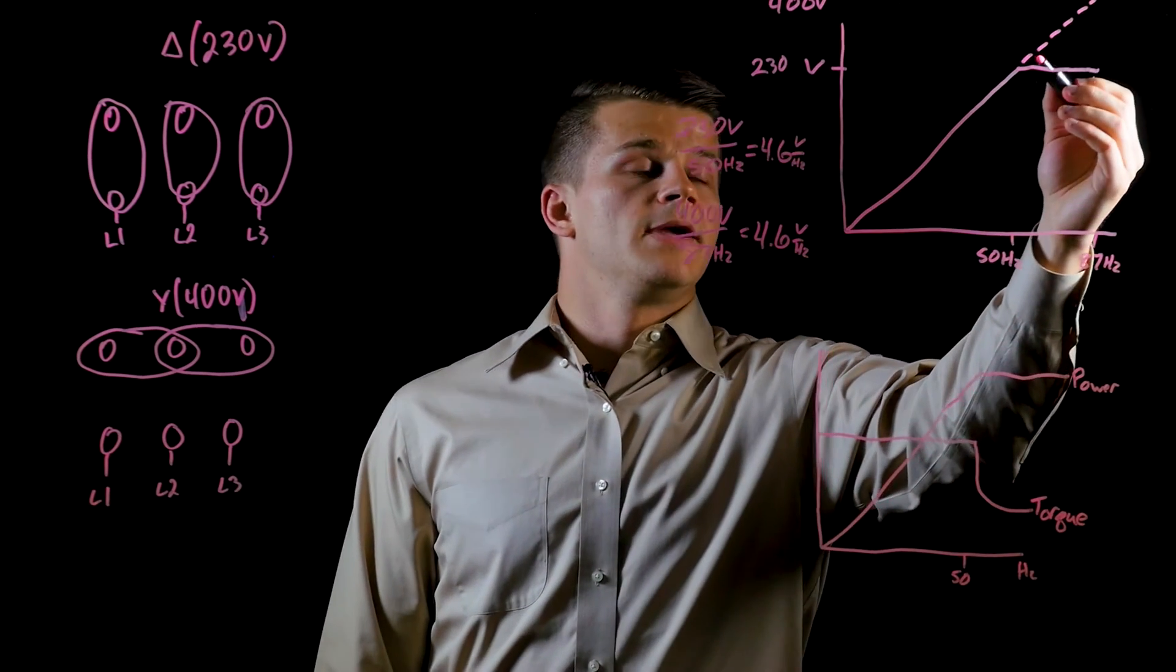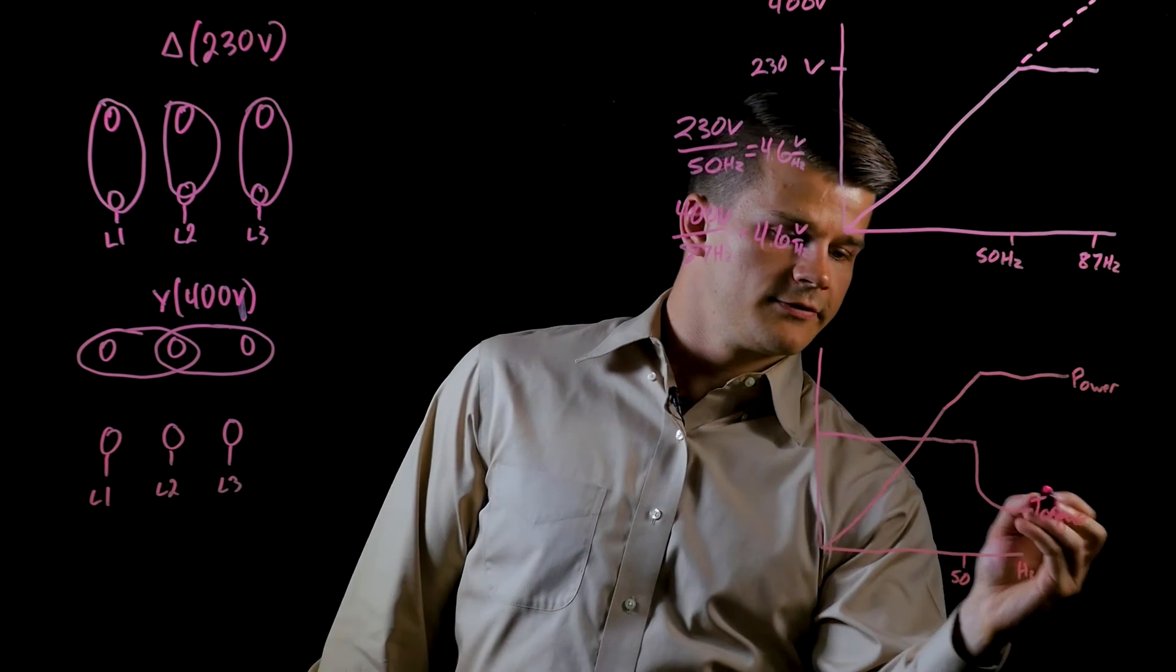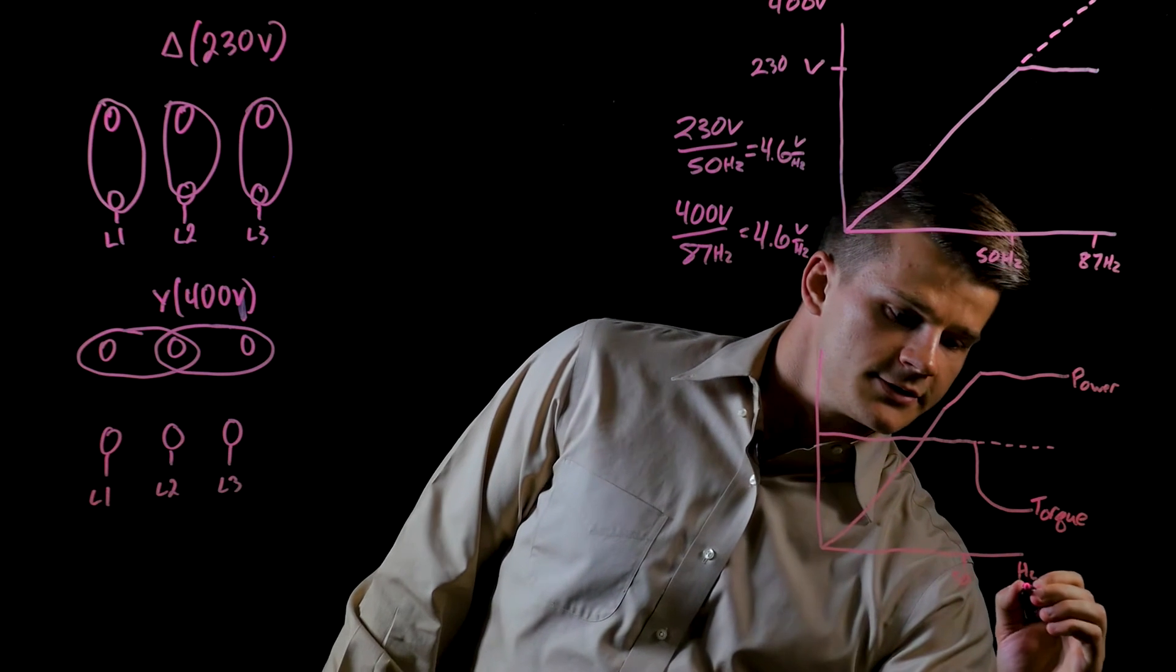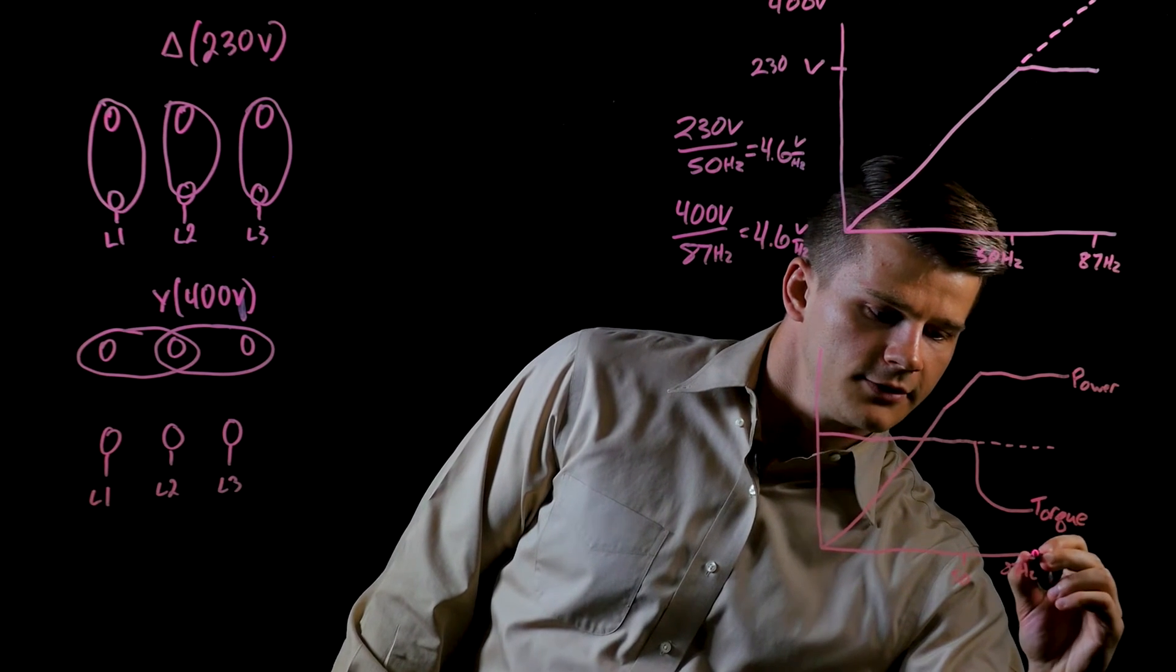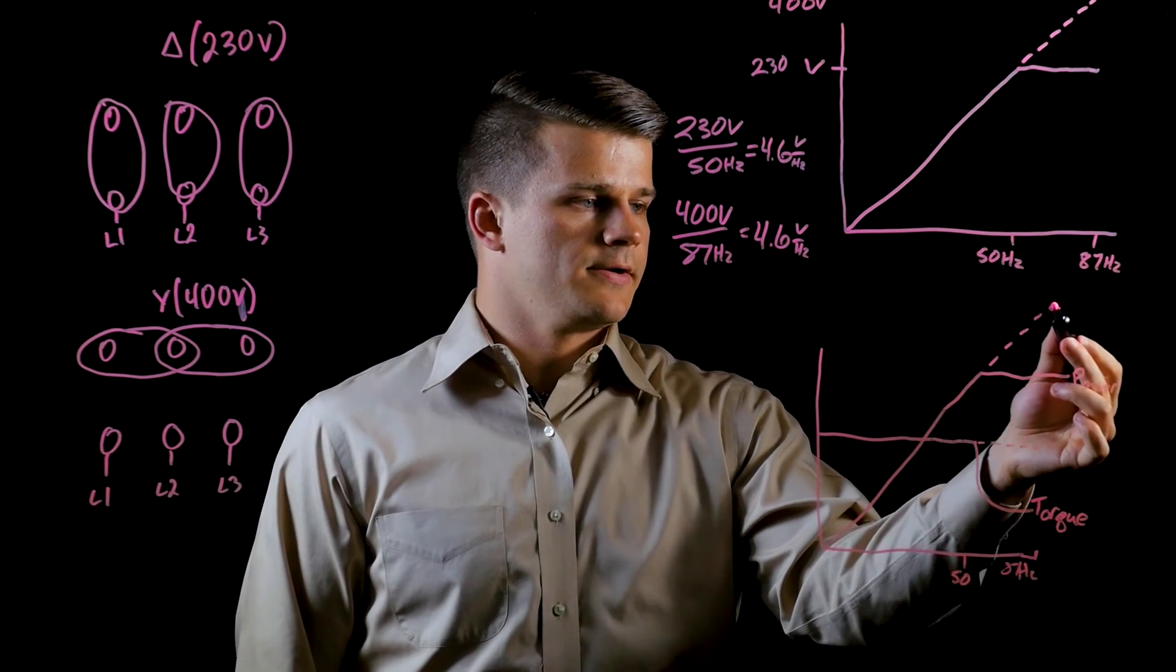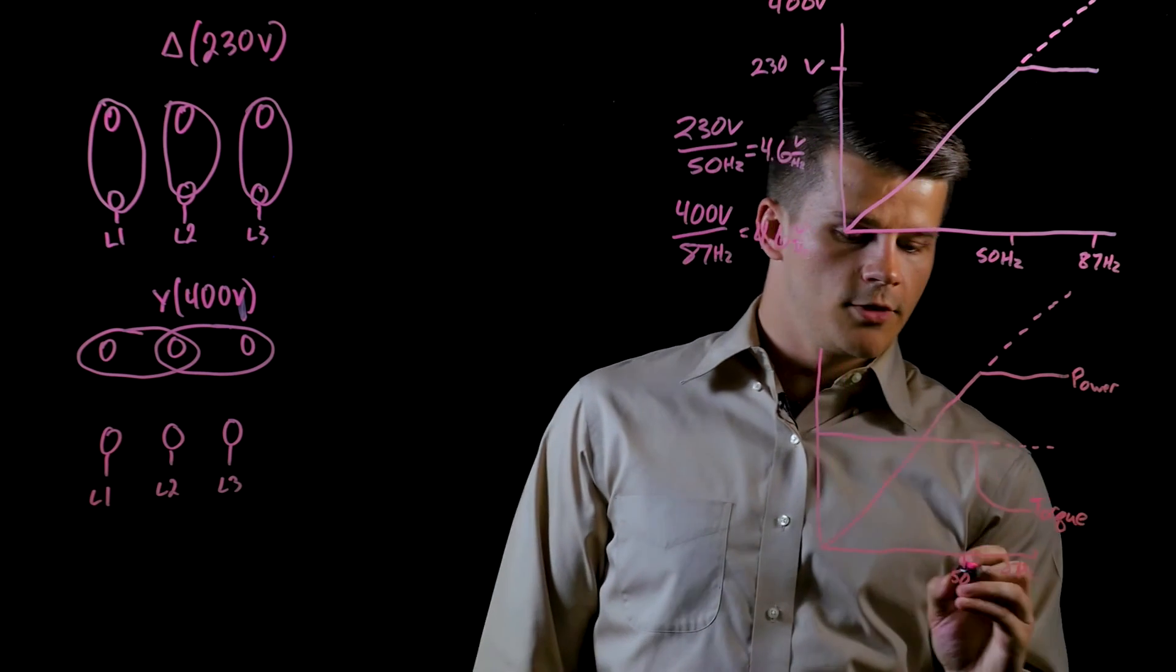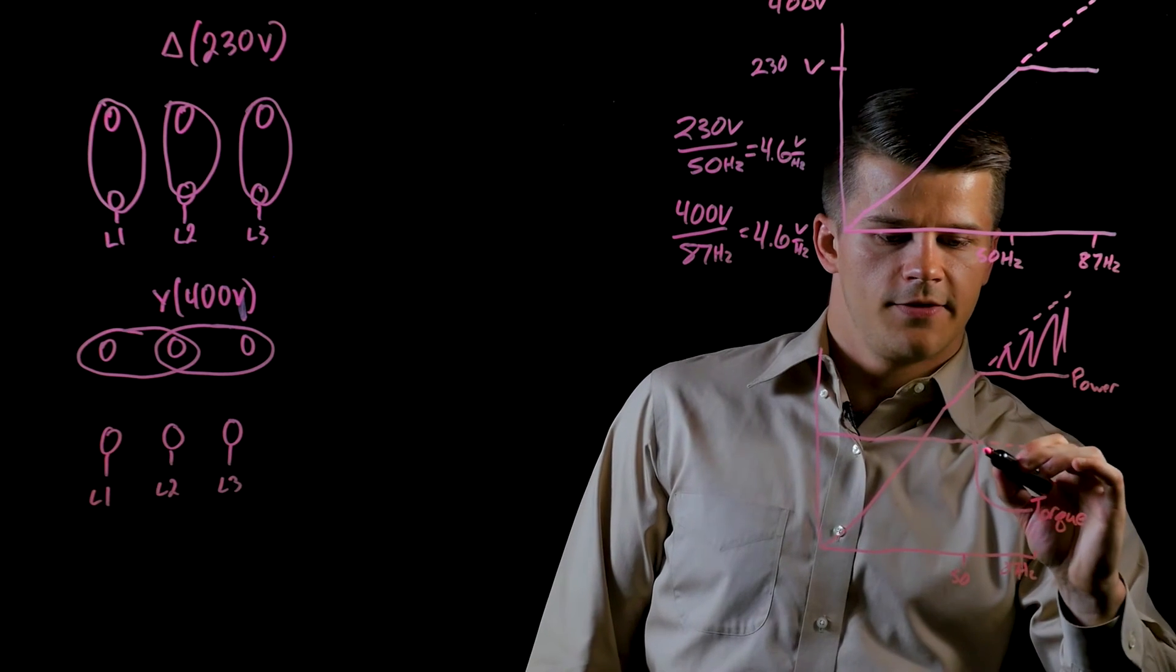Because we're maintaining this ratio constantly from 50 to 87 Hertz, we still maintain our constant torque out to 87 Hertz. The same thing with the power—that also keeps increasing. So as we go from 50 to 87 Hertz, we gain all this extra power and the torque maintains constant.